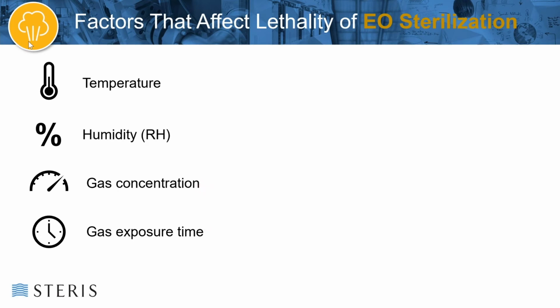So let's look at the factors that affect the lethality of steam. First, we have temperature, then we have humidity, and there's also gas concentration. And can you guess what the last component is? If you could talk, you would probably be saying, yes, it's going to be exposure time. Yes, you're absolutely right. Now, since we're talking about steam sterilization, humidity and gas concentration can essentially be combined into what's called pressure. So the factors that do affect the lethality of steam sterilization are going to be temperature, pressure, and exposure time.